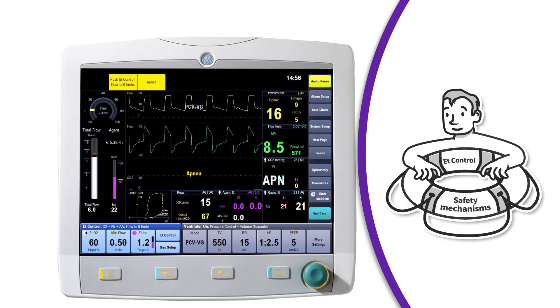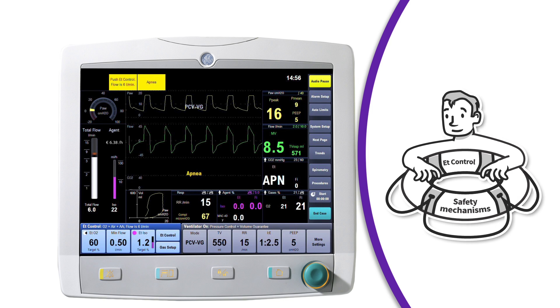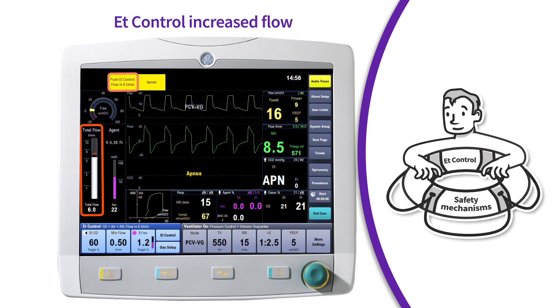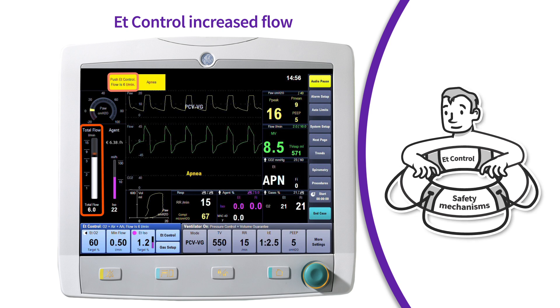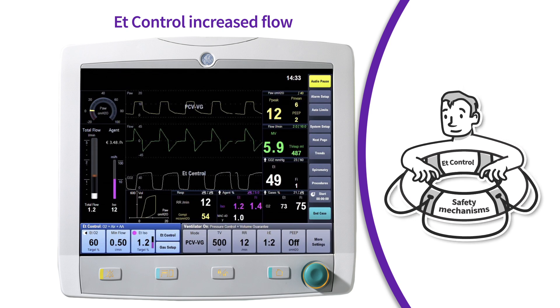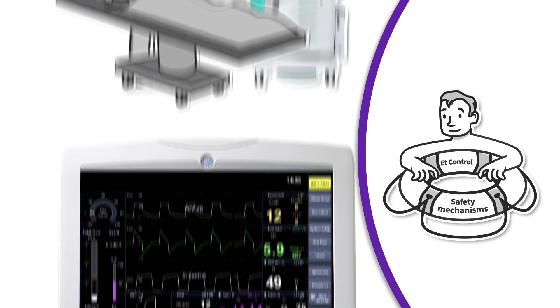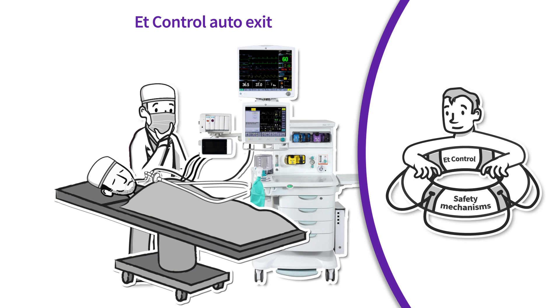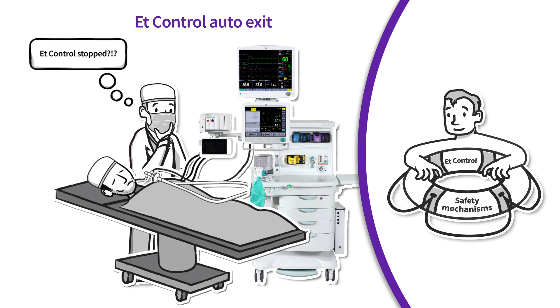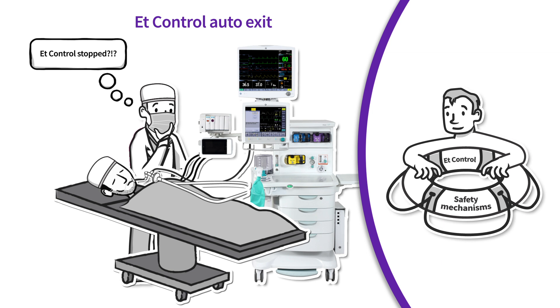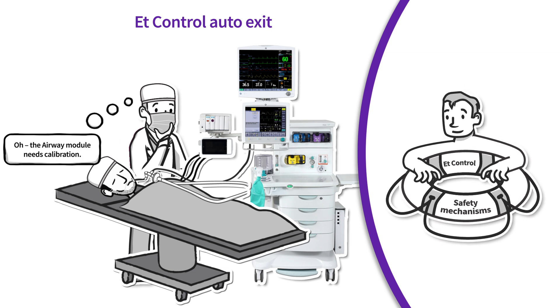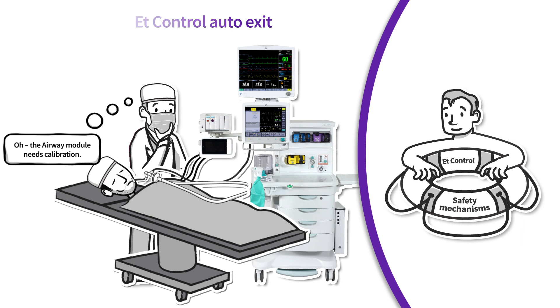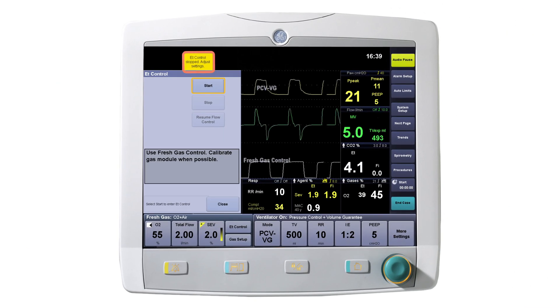With end-tidal control, there are safety mechanisms in place to help clinicians protect the patient. These include the delivery of increased flow when temporary issues arise, such as a leak — end-tidal control will automatically resume when the issue is resolved. Another safety mechanism is automatic exit from end-tidal control when an issue arises that requires clinician interaction or a condition that cannot be resolved during the case, such as an airway module calibration. When this occurs, the system automatically exits ET control and resumes fresh gas control. After an automatic exit, the anesthesia provider will need to manually re-enter end-tidal control.